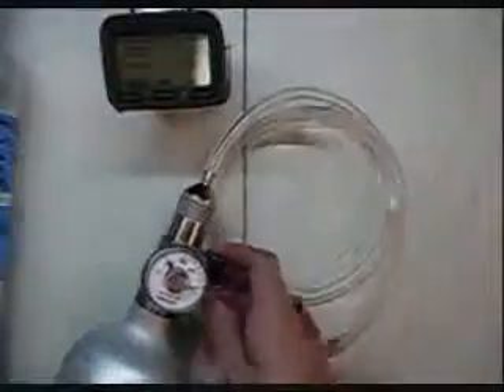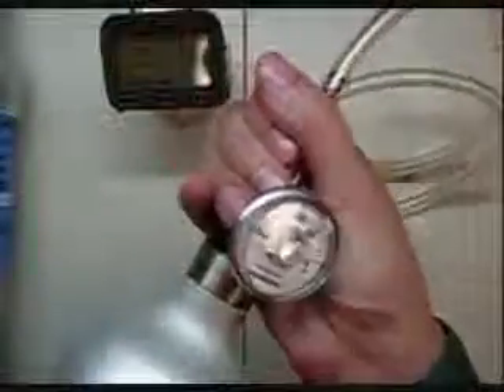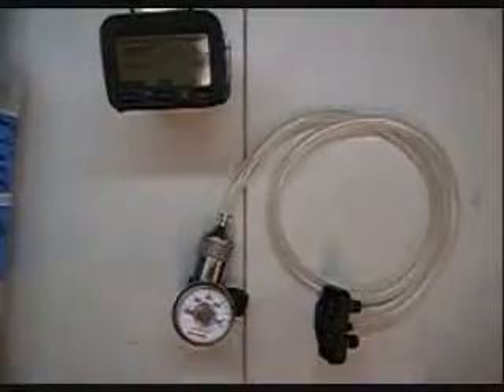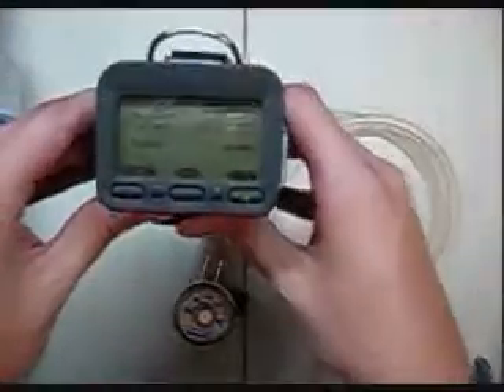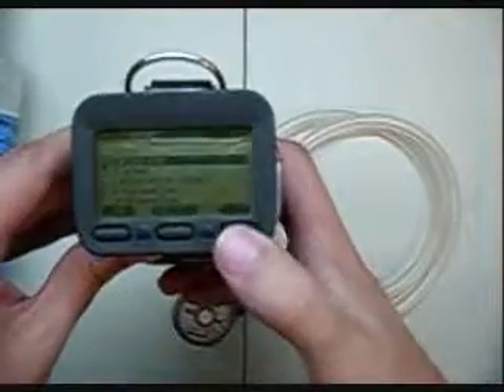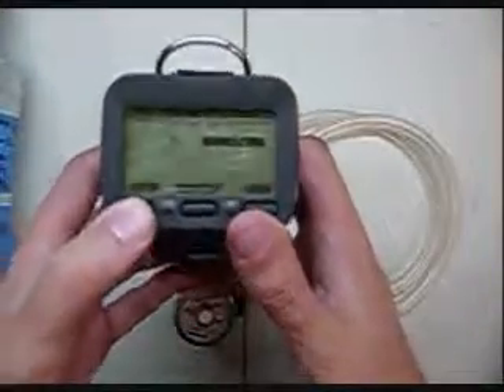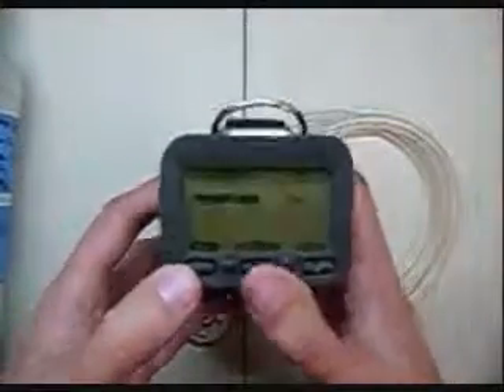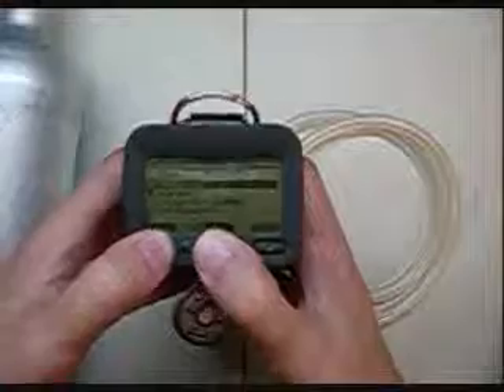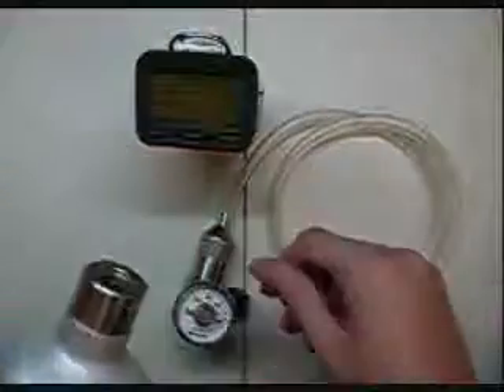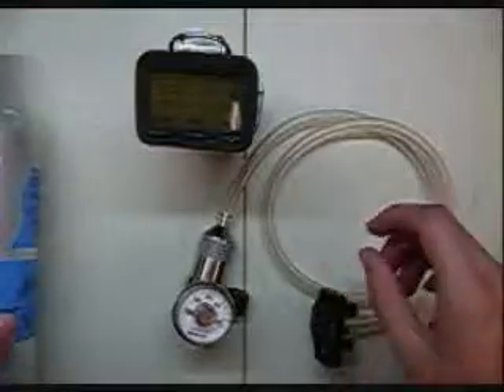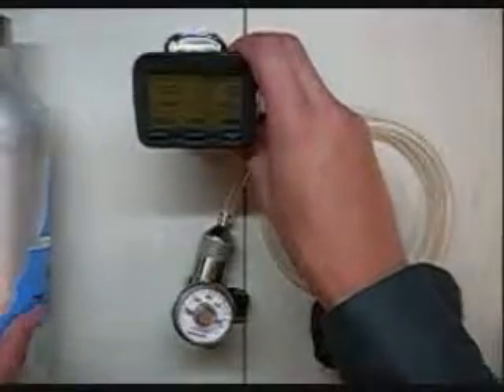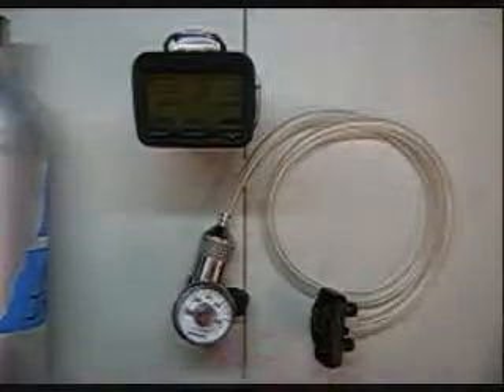Now you can see it's back down to 0, so we'll hit exit, and exit again. If you're going to go directly to the next one, as you can see I only have the 2 sensors here, but all you would do is go down to the next one and do the exact same procedure over again. Select the sensor, go down to calibrate, open up your regulator, screw it in, and then go through the exact same procedure you just went through with the methane. Again, I'd leave about 5 minutes between each calibration in order to let all the gas clear out of there.